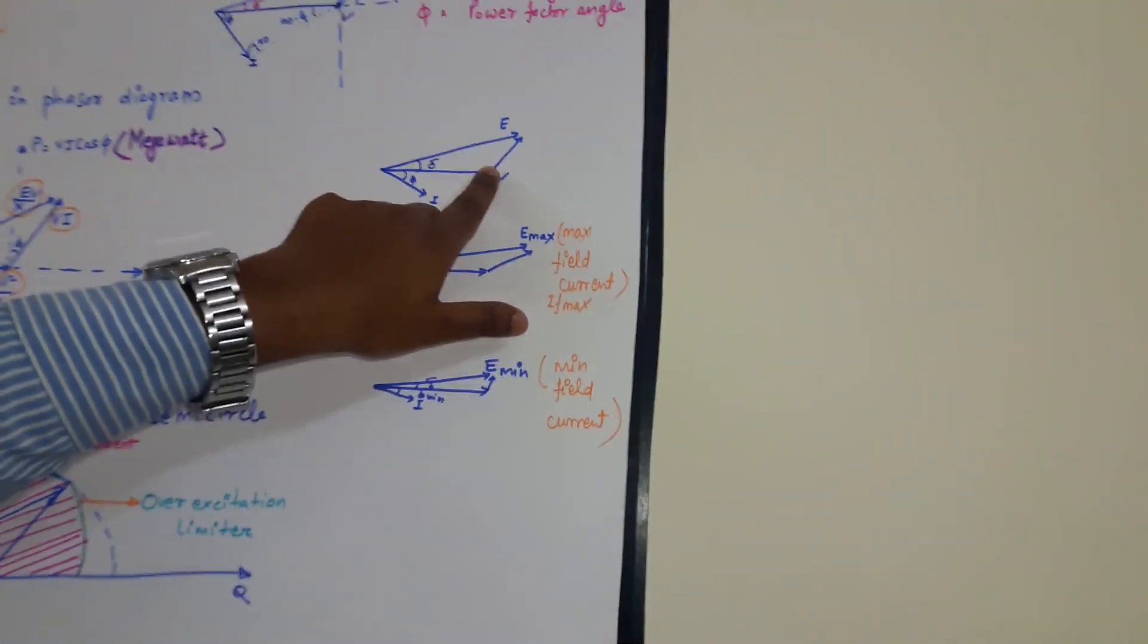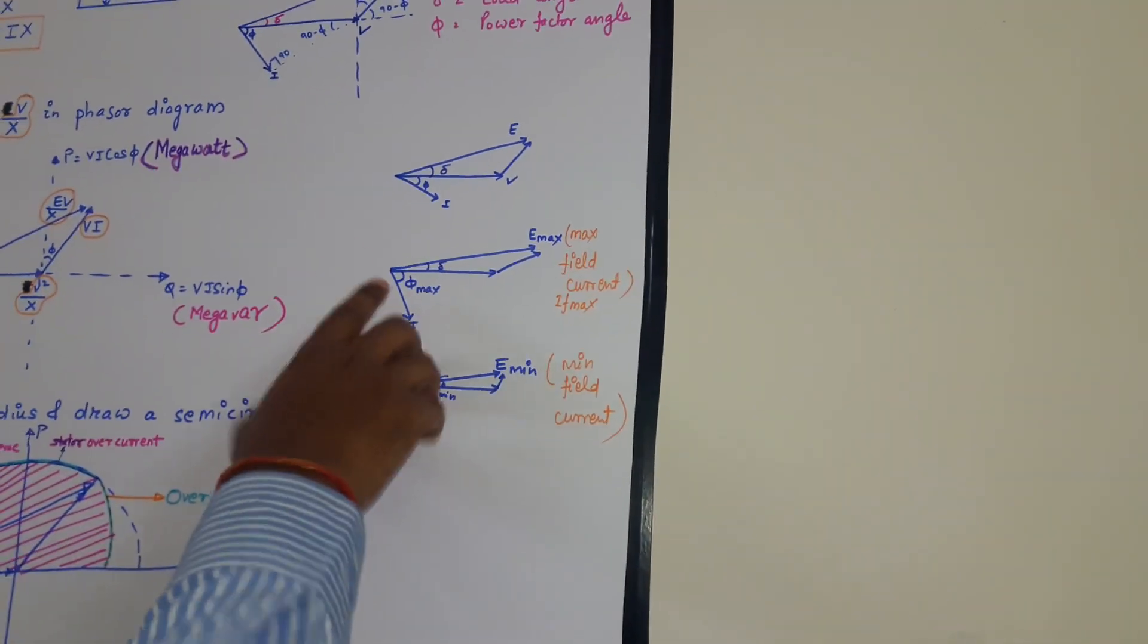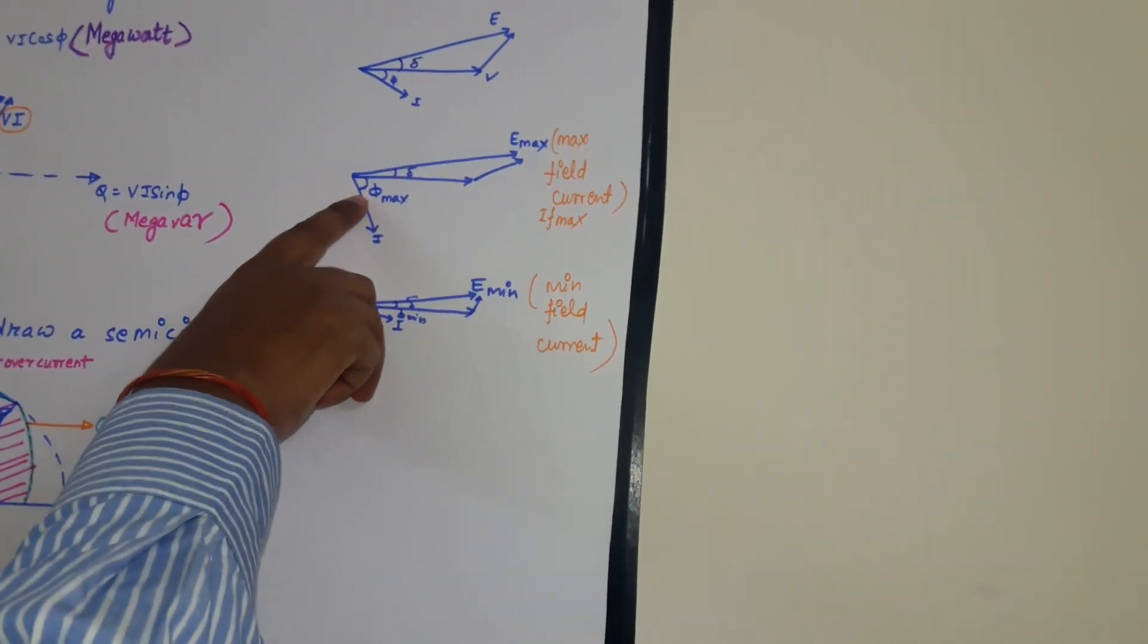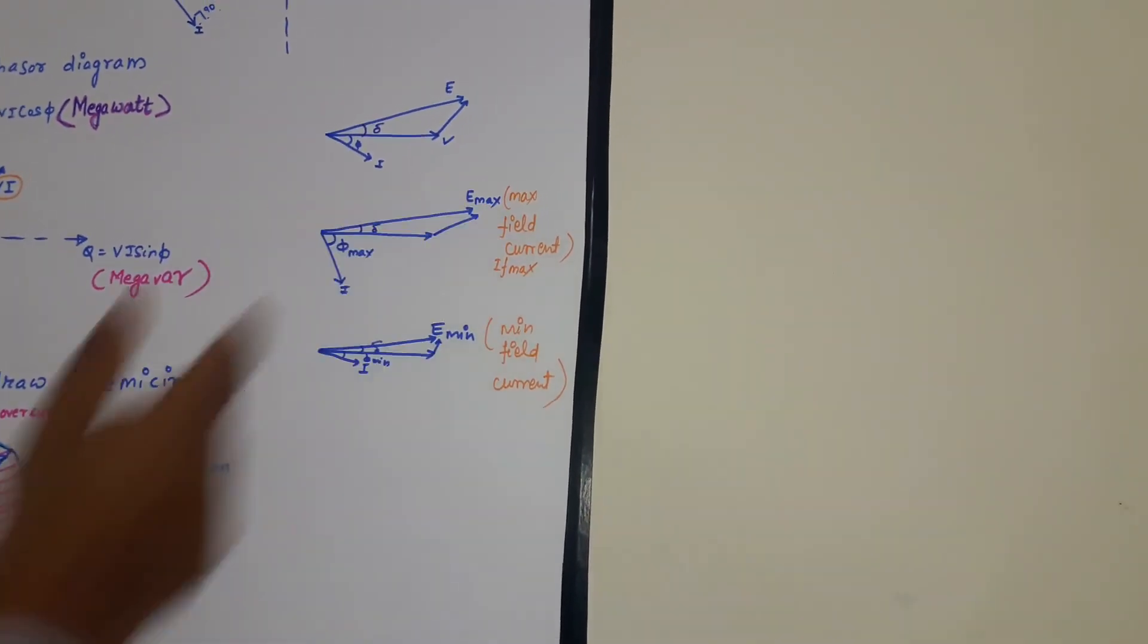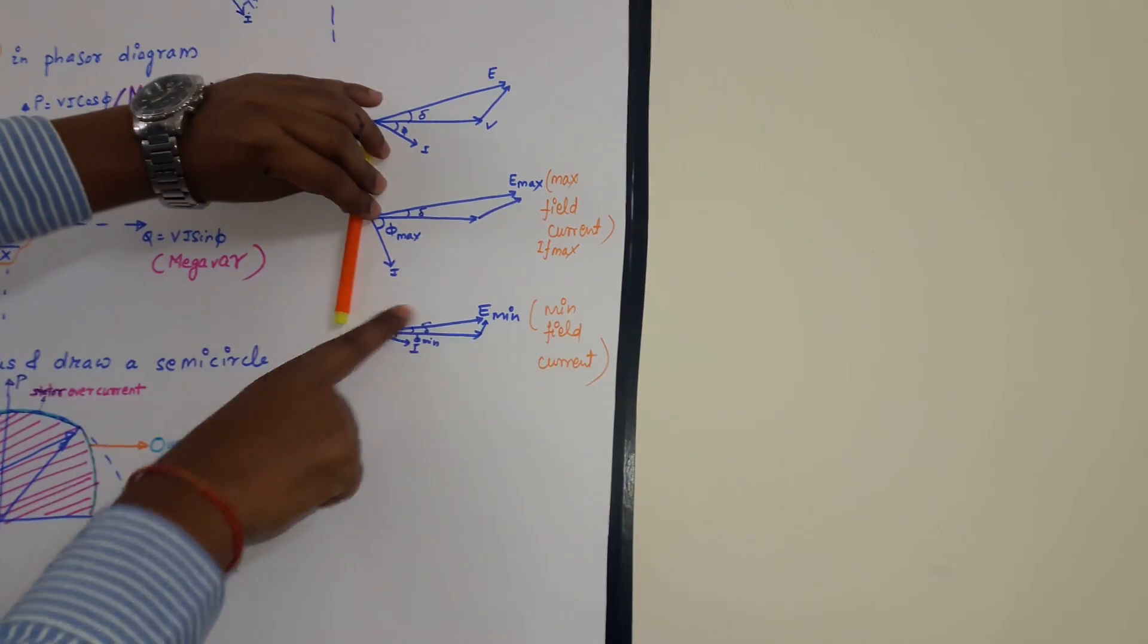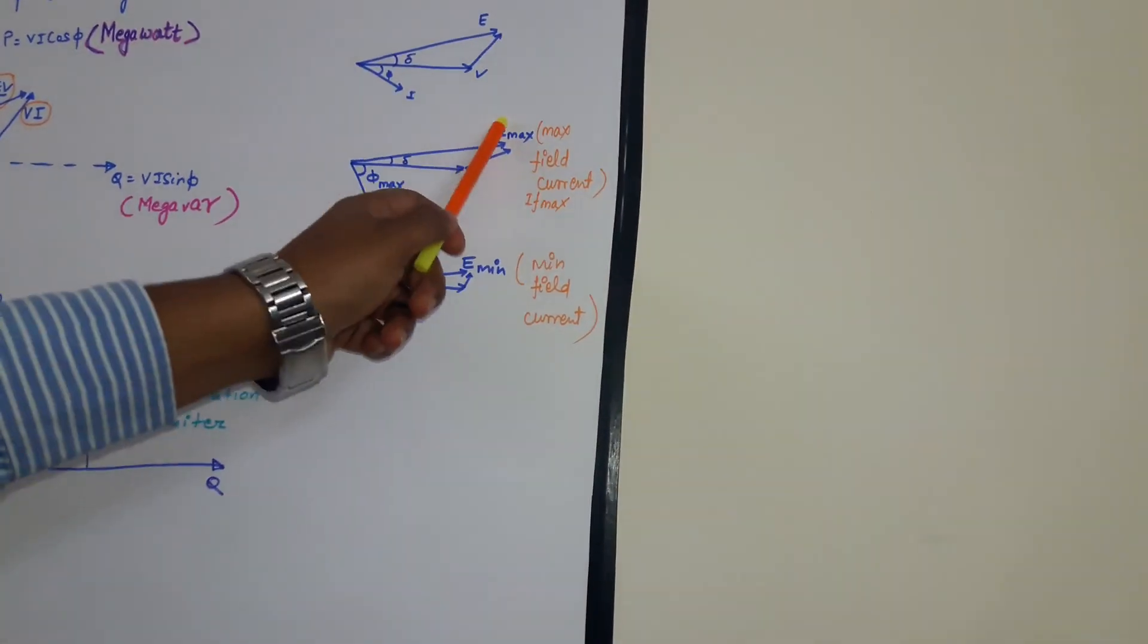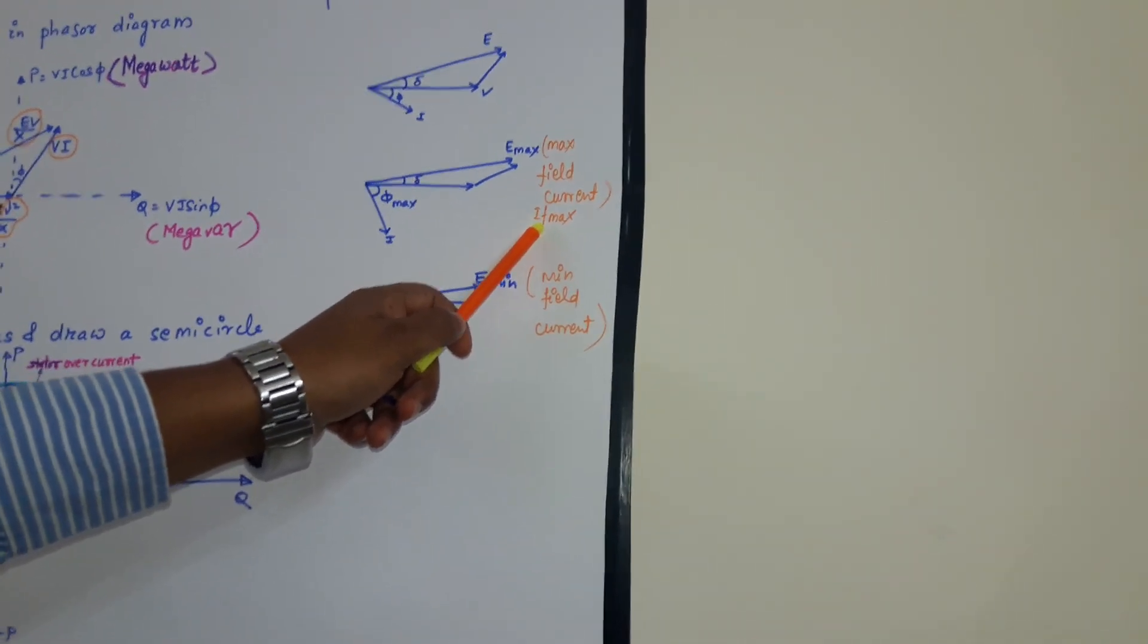When generator is operating at suppose V and E voltage, so suddenly if load increases then my phi, this power factor angle will also increase. And suppose if phi is increasing, that means I have to give more field current to maintain my E. Because phi is shifting to this direction, so my IX it will be shifting to this direction in order to make perpendicular with I. So the length of E is increasing. And if the length of E is increasing, from where we are getting E? We are getting E from the field current. So that AVR will regulate to send more field current to the generator.